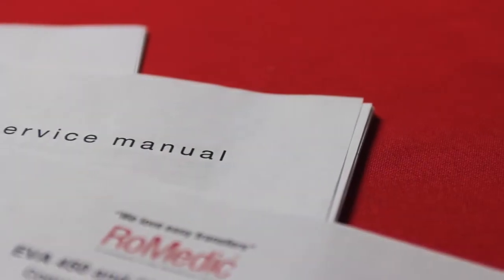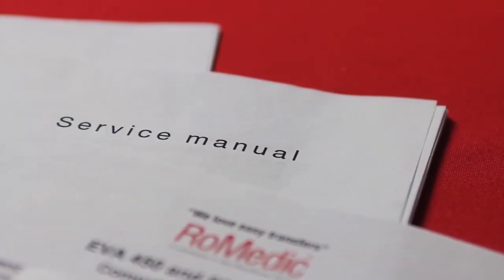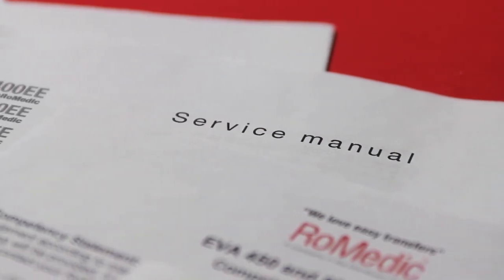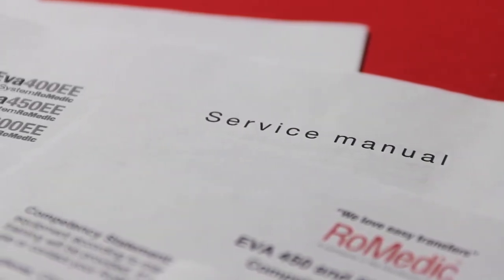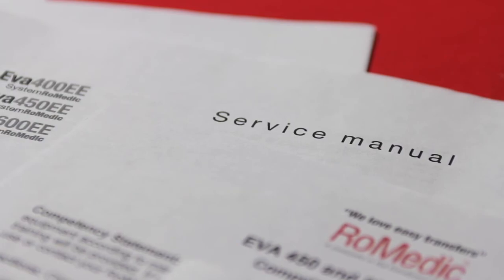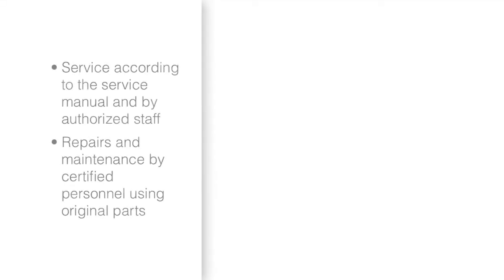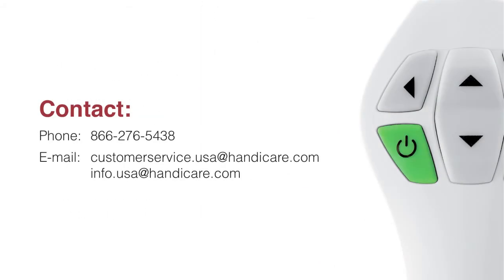The EVA lift should be thoroughly inspected and serviced if needed, or at least once per year. Perform complete weight tests and pay particular attention to parts that show wear, such as joints, bolts, welds, or wheels. Service must be carried out according to the Handicare service manual and by authorized staff. Repairs and maintenance may only be done by trained and certified personnel using original parts. If you have any questions or comments, please consult your local distributor or Handicare specialist.